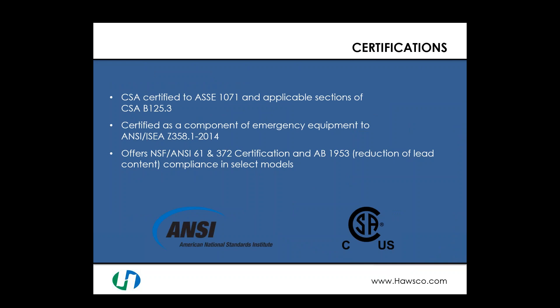The valves are certified to ASSE 1071 — the American Society of Sanitary Engineering standard for mixing valves designated for emergency equipment with safety showers and eyewashes. They are also certified to CSA B125.3. As a component, the mixing valve is certified to ANSI/ISEA Z358.1 2014 because it supplies the tepid water requirement to the equipment. Select models also offer NSF/ANSI 61 and 372 certification, including compliance with AB 1953 regulations for the reduction of lead content in California.